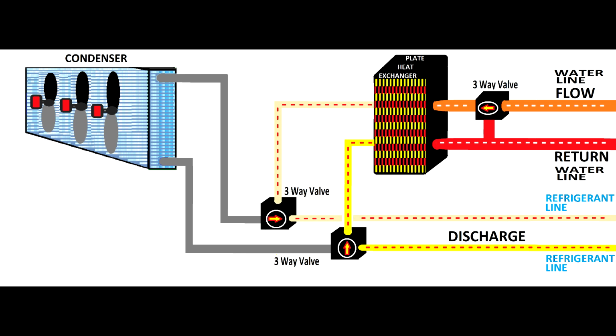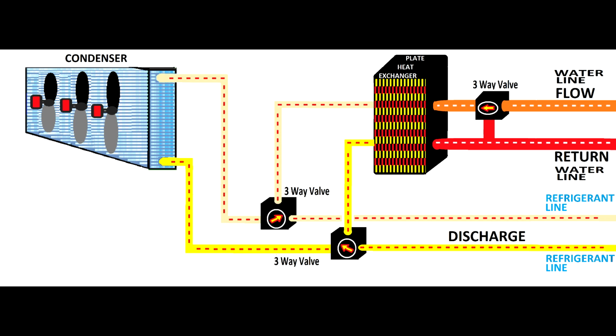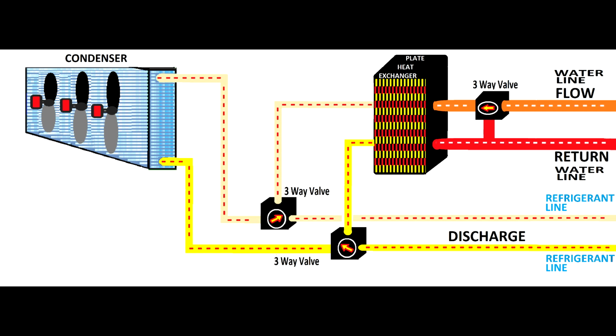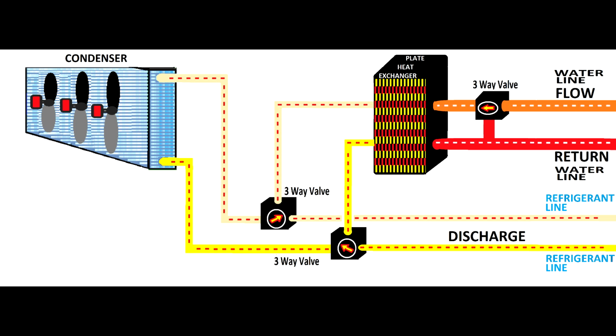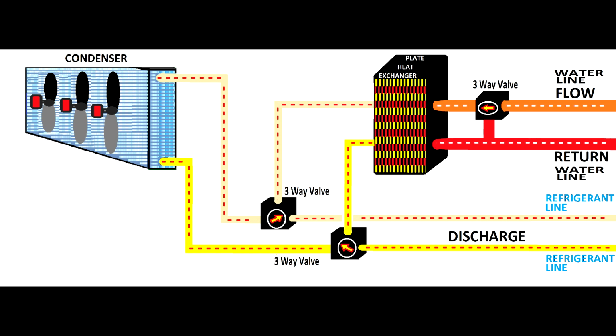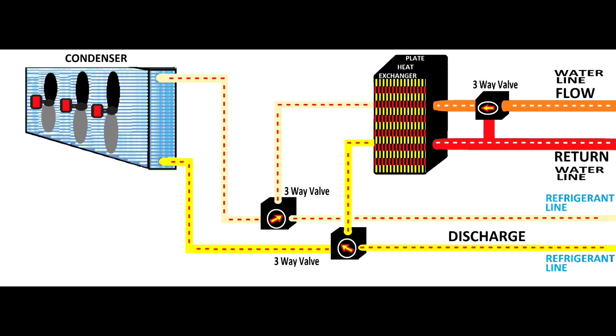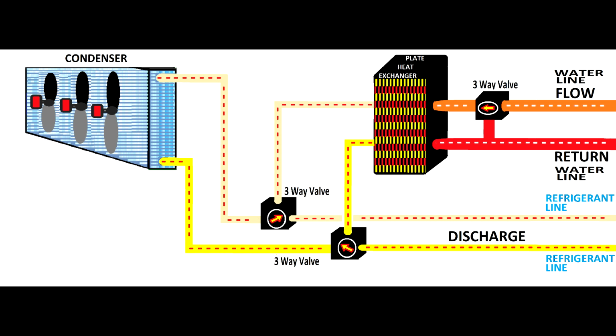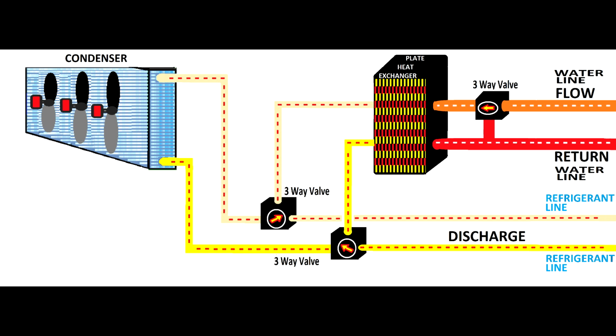That's why you use a lot of three-way valves, and I explained how these three-way valves work and why they are there. If the pressure on the refrigeration system increases, the three-way valve of the refrigerant will divert part of the refrigerant through the condenser, so we can control the pressure. So now we have the discharge, the hot gas, going through the plate heat exchanger, but also part of it goes to the condenser. This is the way we can control the pressure on the refrigeration system.